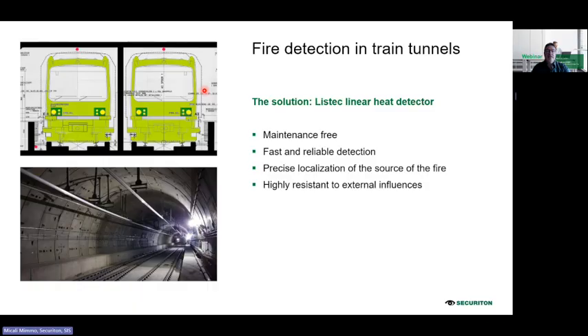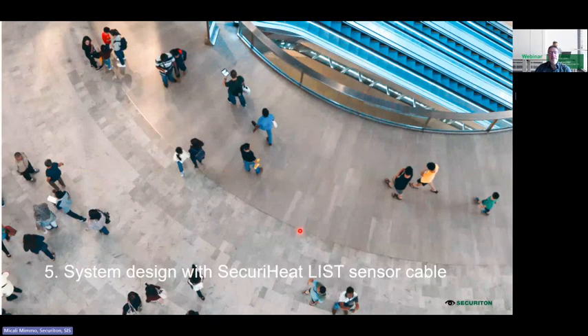Then for that, I think we have the solution. This is our Listec linear temperature detector. Here again, maintenance-free, fast and reliable detection, precise localization of where exactly the fire was detected, so that the fire brigade can reach the exact point of the fire and control it. So let's see the system design of this Listec sensor cable.